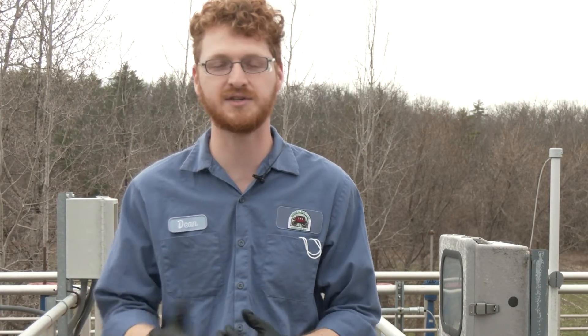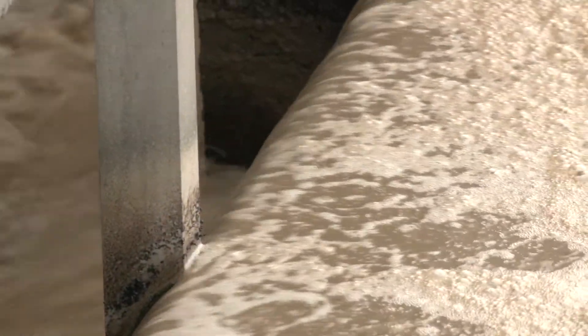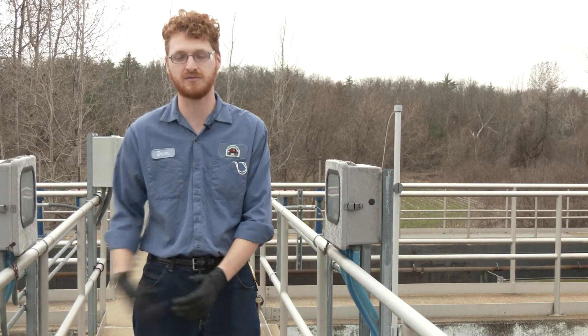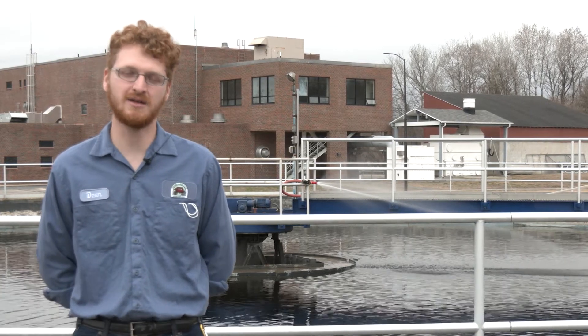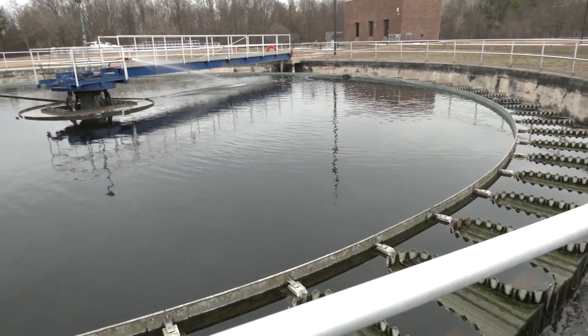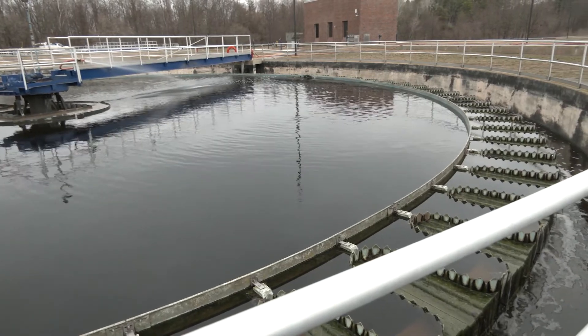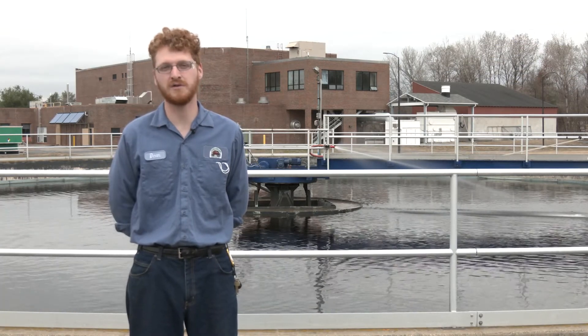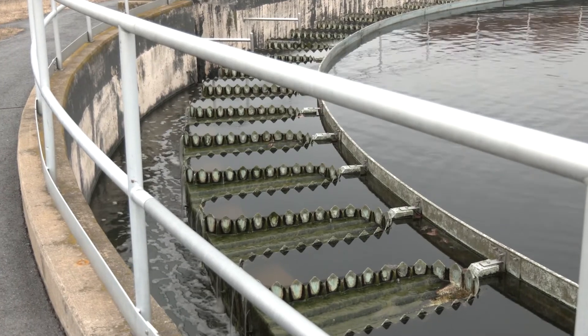The diffusers help distribute the airflow coming out of the air exit location. These tanks are aerated to encourage microbial feeding — the microorganisms that inhabit this tank perform most of our treatment. After the water flows through the aeration basin, it comes to our secondary clarifiers. The purpose of the secondary clarifiers is to settle out the remaining solids. After the solids settle out, the remaining water overflows the weirs and heads to our chlorine building for disinfection.